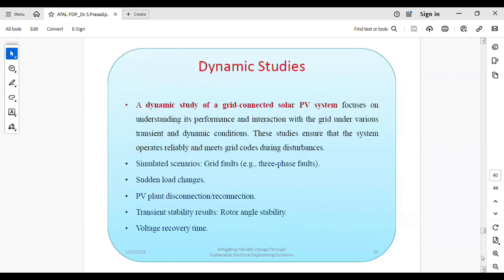And then the dynamic studies, just briefly. Whenever you integrate a solar PV plant to an existing plant where diesel generators are available, you must conduct the transient stability analysis. The generators at the existing plant are there, and now you are going to integrate the PV plant at a bus of the existing plant. Because of the integration, there is a chance the generators will become unstable. Instability may arise because synchronous generators are available, a number of them.